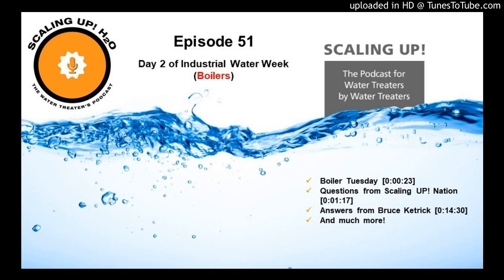We're finding that a lot of facilities are using reverse osmosis for production. Well, if they size them for max production, that means during a lot of the operating period, they have excess RO water. Why not use that in a boiler, since you have to generate with reverse osmosis at a fixed rate? It's not a variable rate piece of equipment, which is why it requires storage tanks. And that's one of the limiting factors, the size of the storage tank and the footprint available.